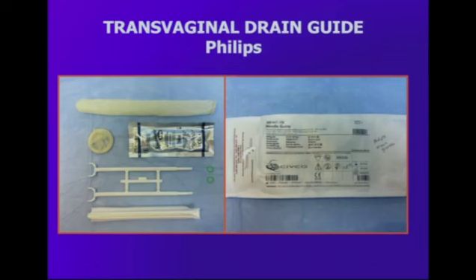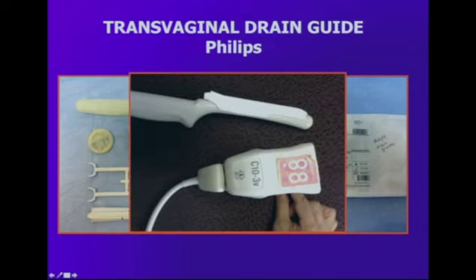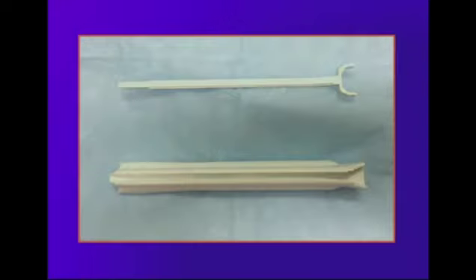Recently, however, a new product has come on the market. It's produced by Civco. This is at the current time only available for either Philips probes or GE probes, and the difference being that this needle guide that you affix to the probe is open along its top. The bore is no longer closed. Again, this is probe specific, so only available for Philips and GE.